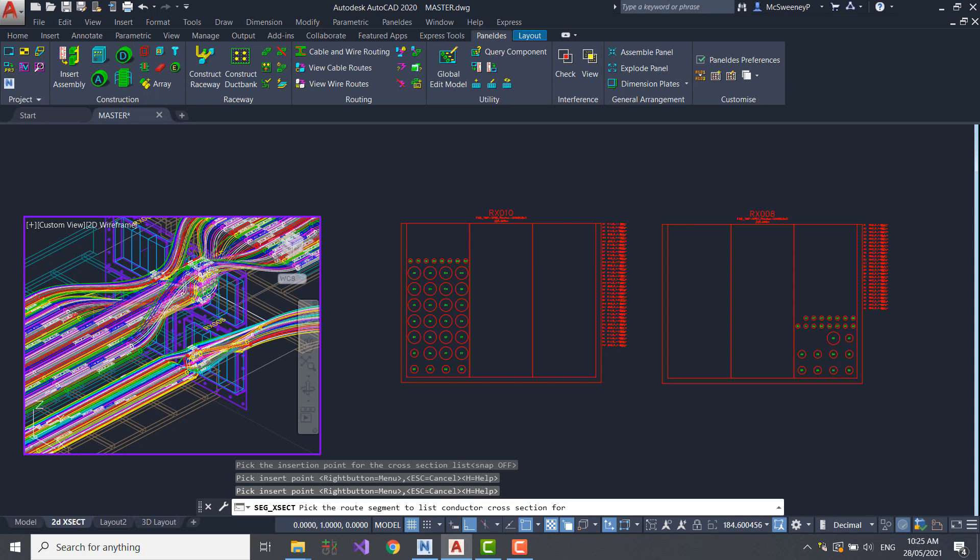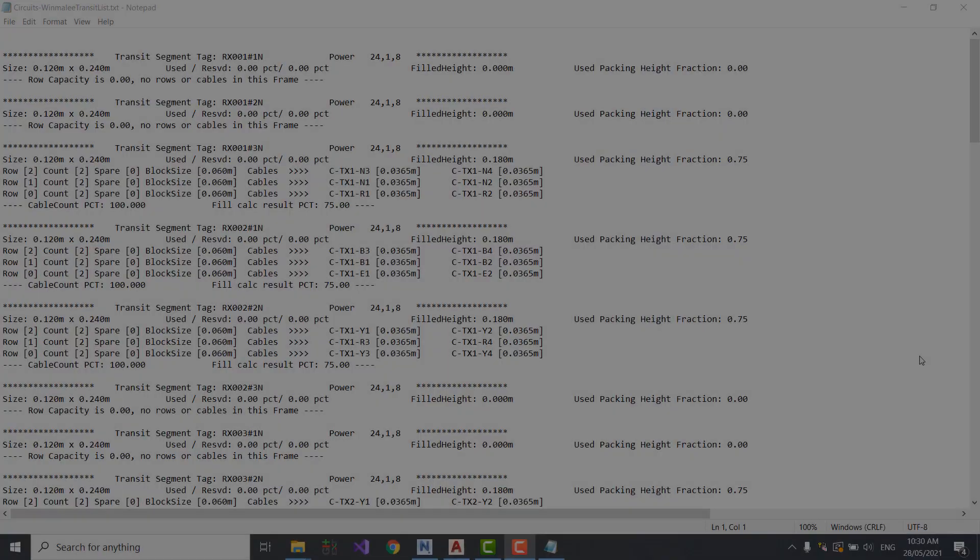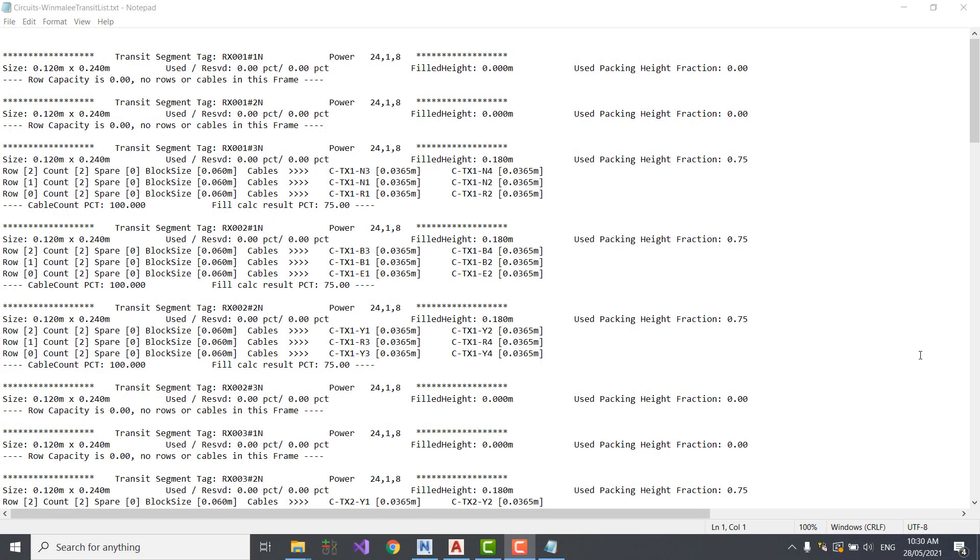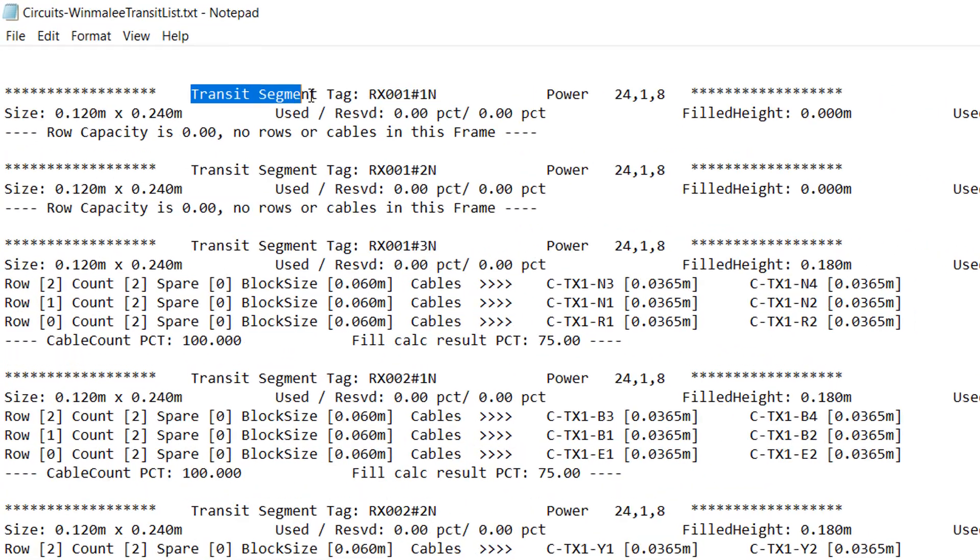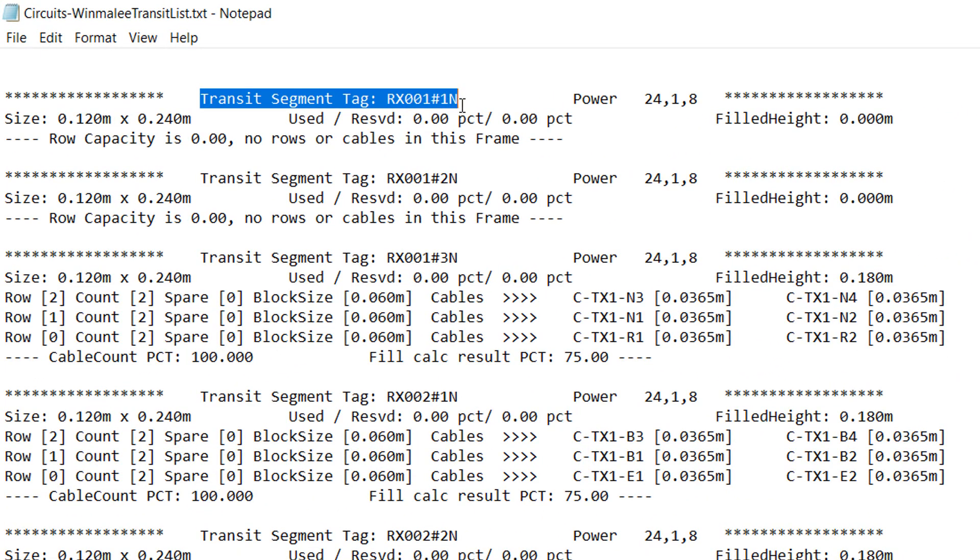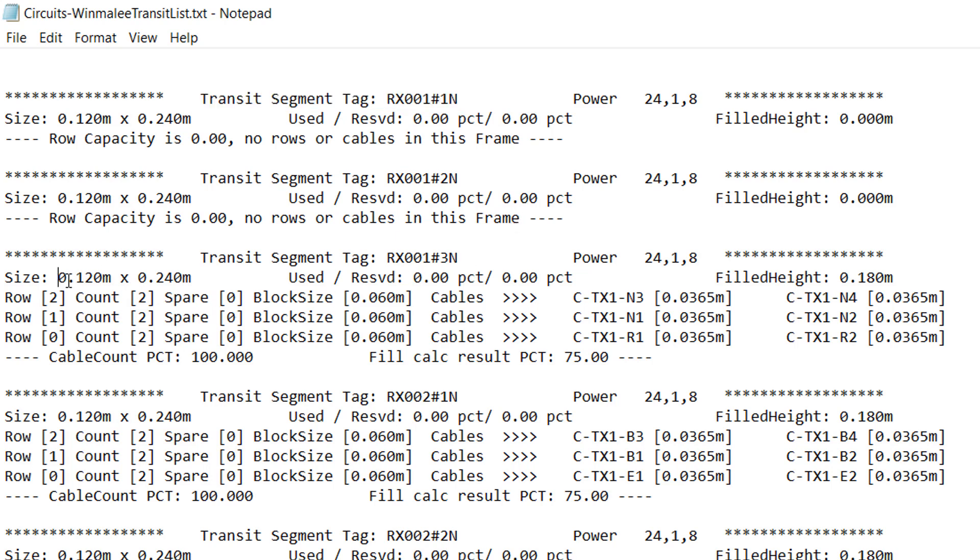During the cable routing process, a transit report is made, and this informs you of the layout and other details for every transit and frame in the project. Every section identifies the transit name. I've highlighted RX1, and after a hashtag, I find the frame name, for example, 1N or 2N. The dimensions of the transit are included.